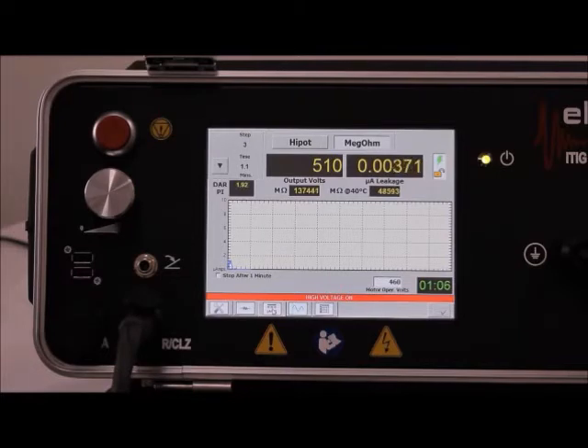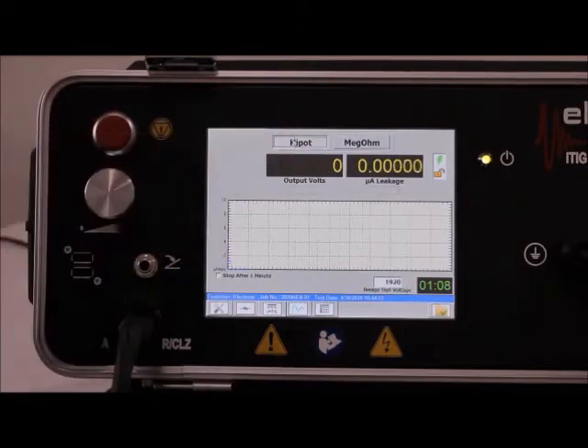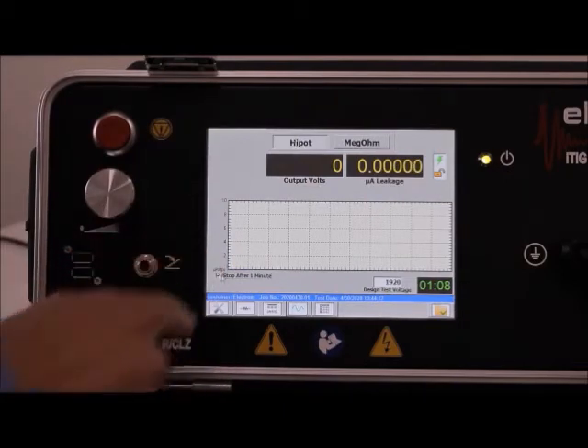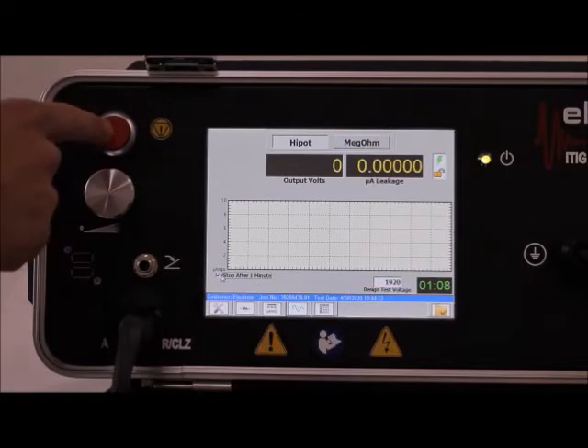DAR at 1.92. That's good. Red button, shut off the test, automatically discharges the windings. Next step, hipot test. Hipot screen, similar to what we just did. I'm now going to select the stop after 1 minute, hit the red button.